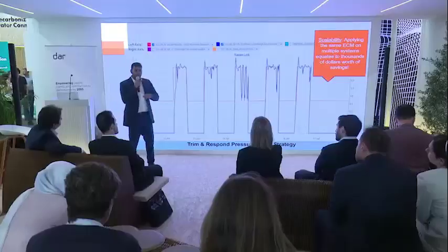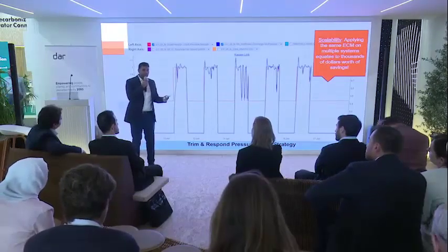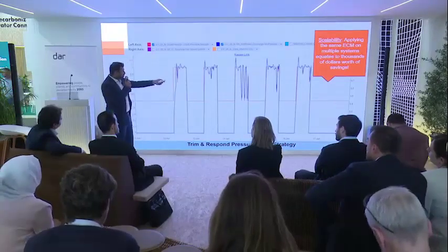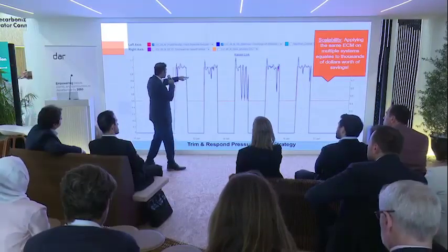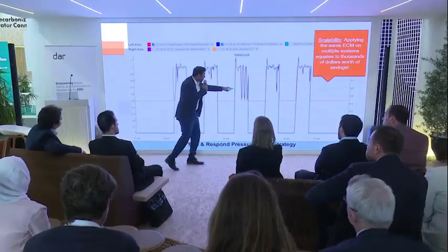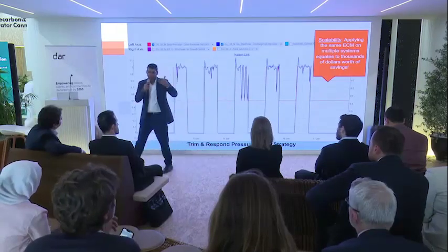In this case, what we did with ASO is you had a situation like this. Well, ASO can actually look at what's happening in the zones where real human beings are. And when there isn't enough demand, you can begin to reset your pressure. And when you begin to reset your pressure set point, that's the red trend log, you can see the pressure actually follows the set point. All to say, when that happens, your fan is running at a reduced speed.